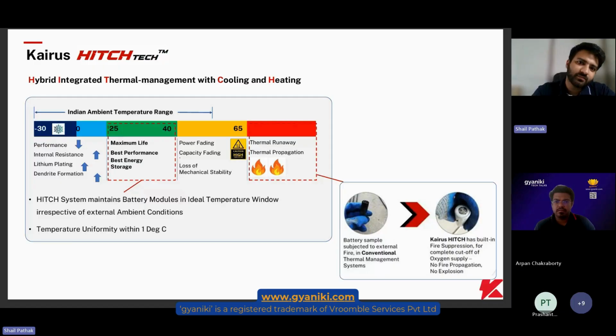Explosion takes place by three things coming together. You need a medium for fire propagation, you need the fuel, which is the cell, and oxygen. When this triangle gets completed, there is an explosion which cannot be avoided. So if you break this triangle in any kind of application, you will be able to break the fire triangle, and there won't be any thermal runaway.